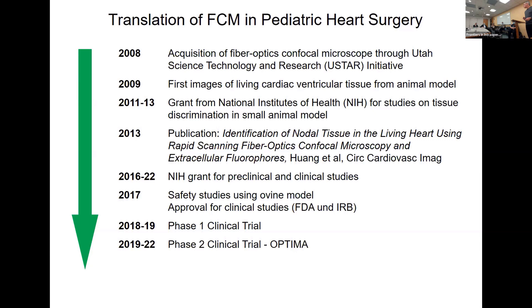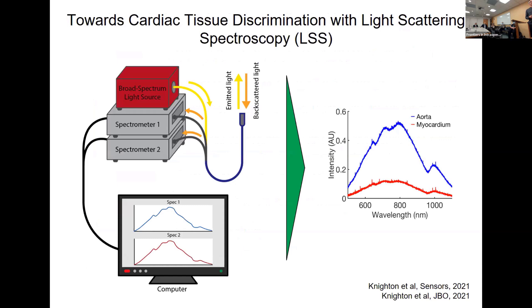I will now show you another idea on tissue discrimination — what kind of technologies can be applied. This technology could do something similar to FCM, be easier to apply, and is likely orders of magnitude smaller in investment. What we developed is a system that uses a broadband light source, works with optical fibers, shines light into the tissue, and the tissue scatters the light back. We have two spectrometers that sense the backscattered light at different distances, giving us two different spectra.